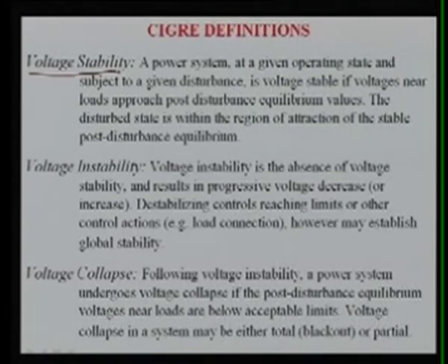Here in voltage instability, what happens? There is a possibility that the voltage of a few areas, a certain zone, may increase or decrease heavily, and that may destabilize the control actions. We have a lot of devices that work on voltage measurement. If the voltage is low, an undervoltage relay may operate, pick up, and give a trip command to the load shedding, etc. Because undervoltage or underfrequency relays are there, and they normally go for load shedding, so it may go for load disconnection. Then what will happen? Then it is called voltage instability, meaning voltage has gone excessively lower or higher than its prescribed limit.